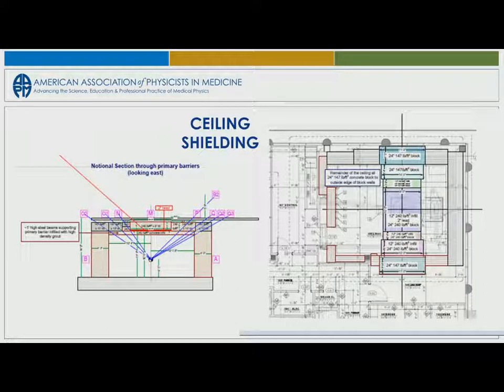Now, your challenge can be your ceiling. This is what I call the nightmare ceiling. You can't have a bump out. It was an existing building. So you can't do your traditional bump out. You can't do a bump down because you hit the linac. You have to have room to rotate the linac. So if you can't bump up or you can't bump down, how are you going to get the shielding in there? Well, you have no choice except to go with the high density concrete or lead to make up that thickness. You can do a 4-foot ceiling all the way across and do it with about 13 to 14 inches of lead and the rest of it concrete, and you can make one uniform ceiling thickness of 4 feet all the way across.